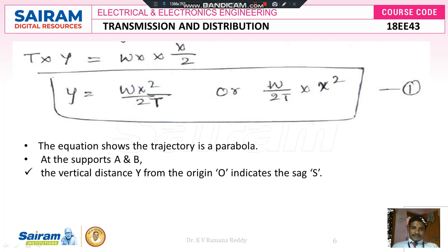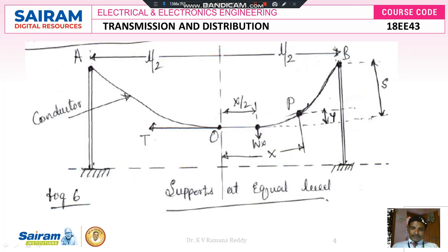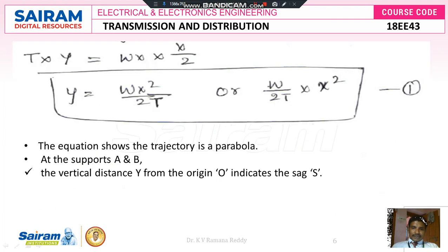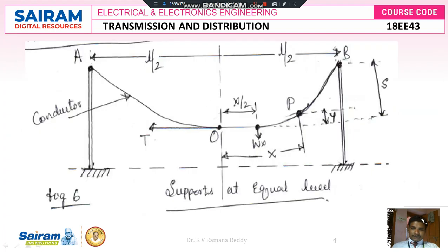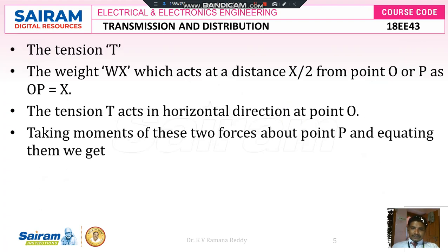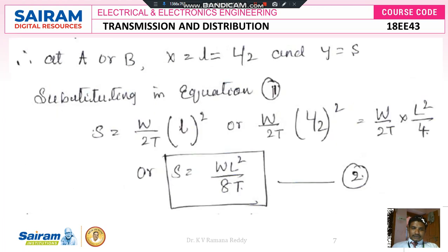If we send T to the right-hand side, then y = wx²/2T, or y = (w/2T) × x². This equation shows the trajectory is a parabola. At supports A and B, the vertical distance y from origin O indicates the sag S. Looking at the figure, the vertical distance from the center to point P is y, so we can replace y with S.